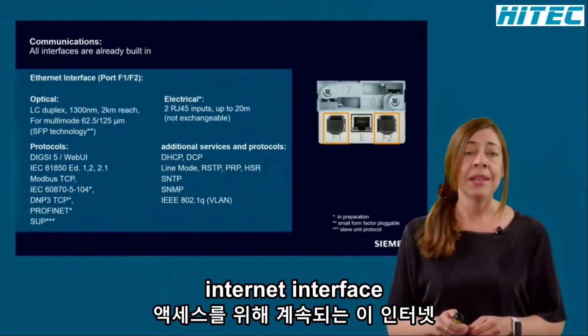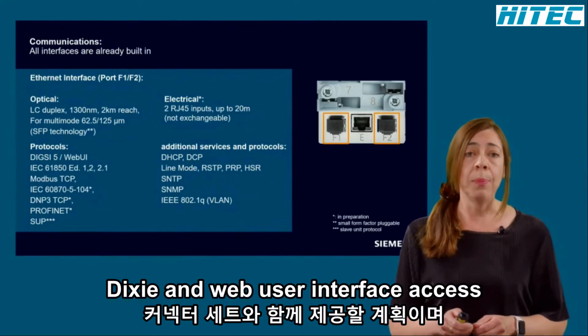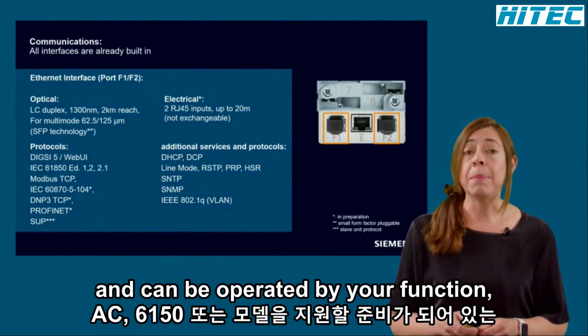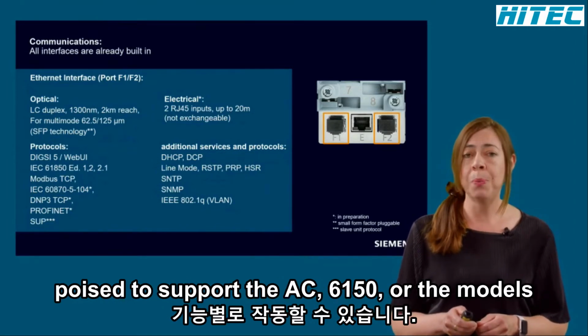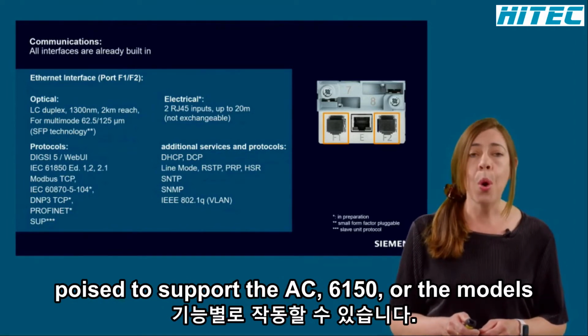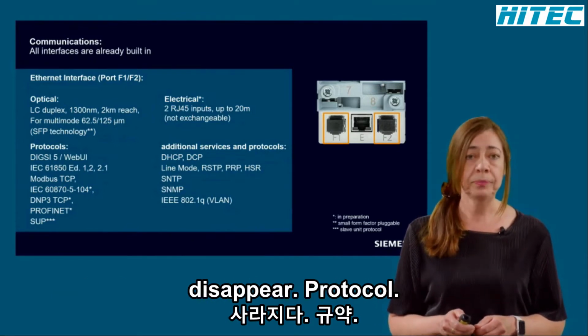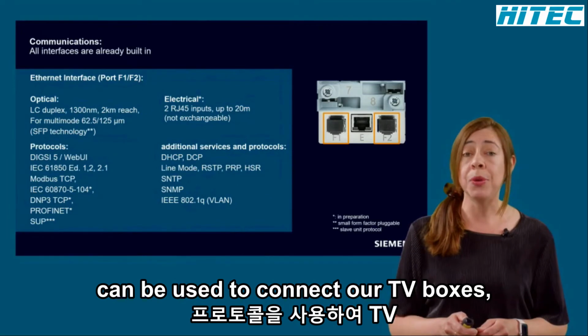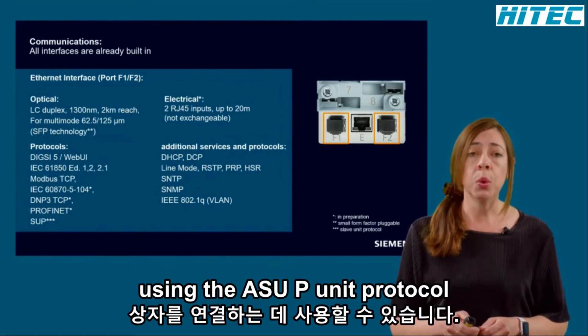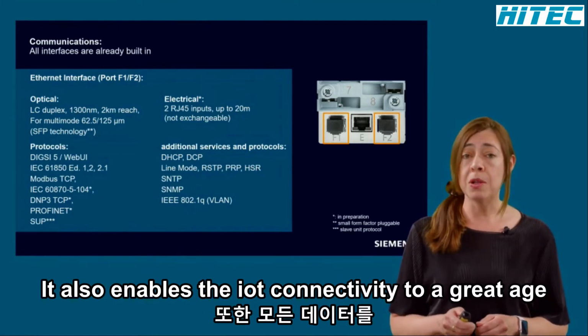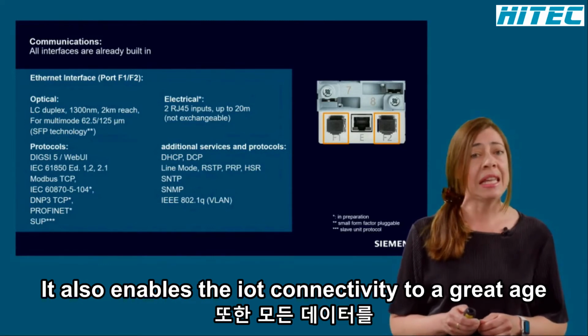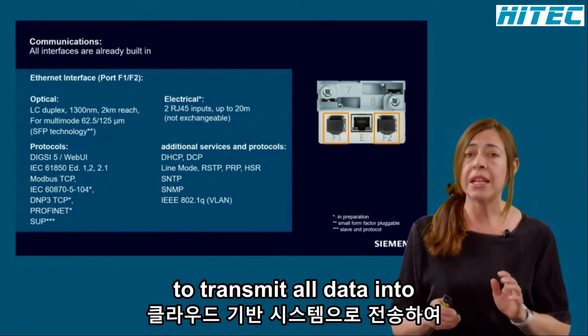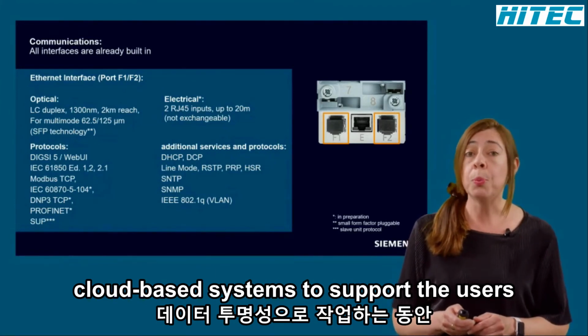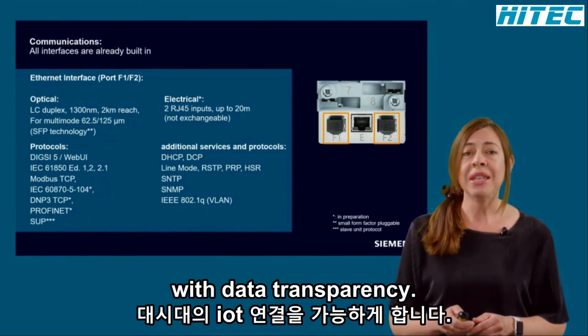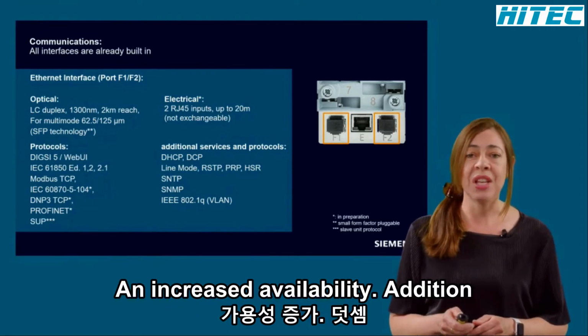This Ethernet interface can be used for remote DIGSI and web user interface access and can be upgraded via function points to support the IEC 61850 or the Modbus TCP protocol. Furthermore, the interface can be used to connect RTD boxes using the SUP, Slave Unit Protocol. It also enables the IoT connectivity to a grid edge to transmit all data into cloud-based systems to support the users during the operation with data transparency and increased availability.